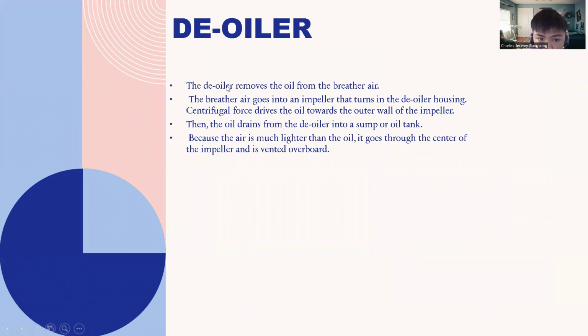Next is de-oilers. The de-oiler removes the oil from the breather air. The breather air goes into an impeller that turns inside the de-oiler housing. Centrifugal force drives the oil towards the outer wall of the impeller. Then the oil drains from the de-oiler into a sump or oil tank. Because the air is much lighter than the oil, it goes through the center of the impeller and is vented.